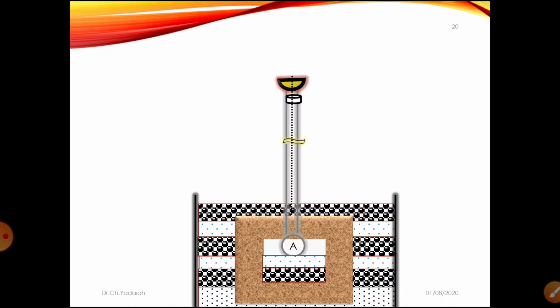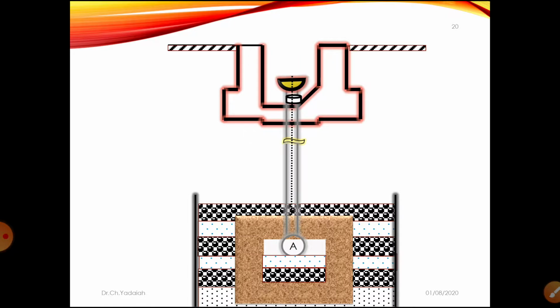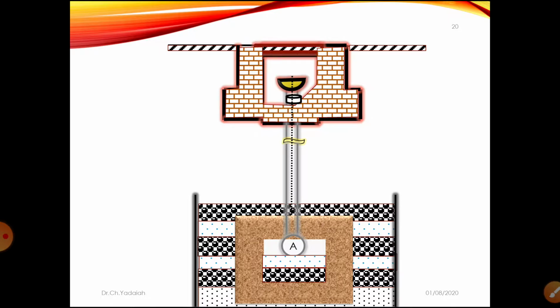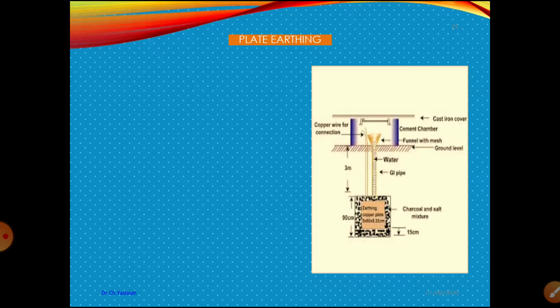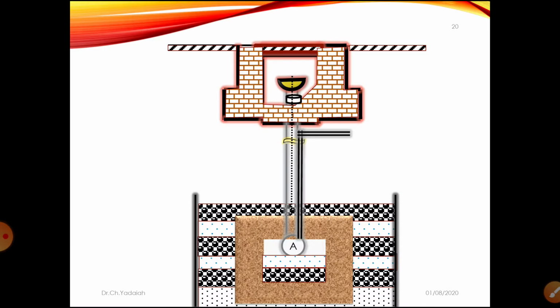After that we connect the mechanical arrangement, the concrete arrangement we've seen before. The connections also use 30 centimeters, all dimensions as you know. Now close the concrete arrangement and cover it with cast iron for protection and opening purposes. This is the full arrangement. Now I will connect a 12 mm GI pipe here for the earth connection to the switchboard. Everything is the same, dear students, please practice it.